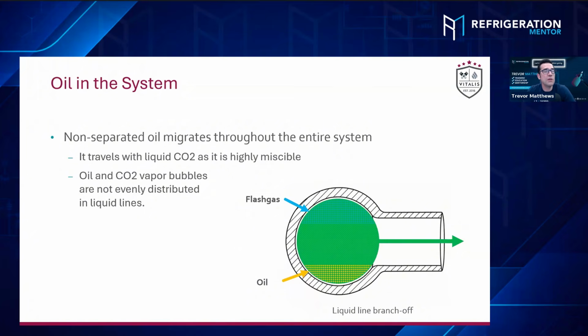Okay, perfect. And I know this is a bit off topic. Does it make a difference between now an overfeed system or a CO2 pump system versus a transcritical system? Yeah, 100%. On the pump system or liquid overfed system, you typically have to consider way less the oil return. And even if you produce oil slugs, it doesn't really matter because the system is designed to handle an overfed liquid mass flow, right? So you have big liquid accumulator vessels sitting on top of the pump. So you just circulate all the liquid and the oil, and that's not a big deal with the oil return.